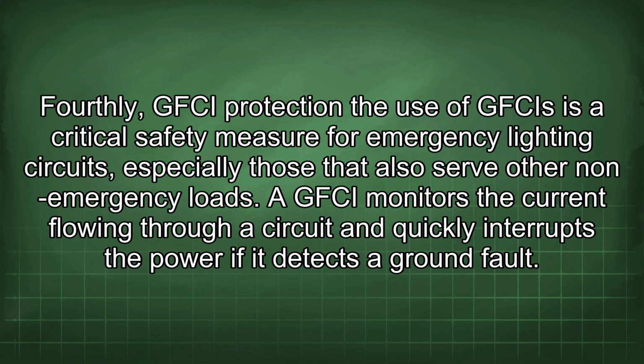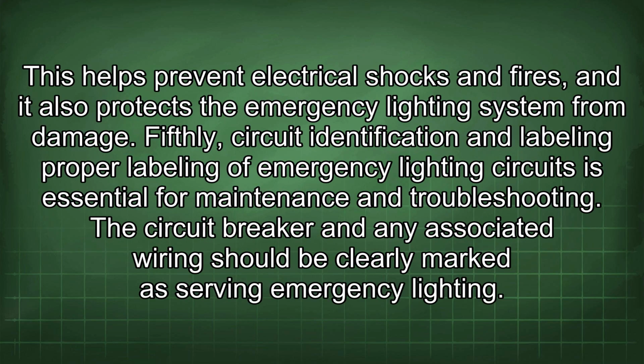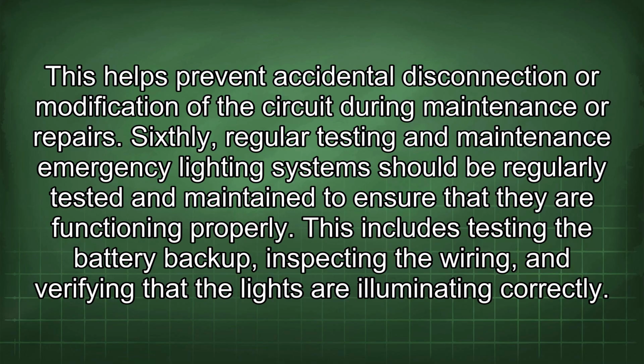Fourthly, GFCI protection. The use of GFCIs is a critical safety measure for emergency lighting circuits, especially those that also serve other non-emergency loads. A GFCI monitors the current flowing through a circuit and quickly interrupts the power if it detects a ground fault. This helps prevent electrical shocks and fires, and it also protects the emergency lighting system from damage. Fifthly, circuit identification and labeling. Proper labeling of emergency lighting circuits is essential for maintenance and troubleshooting. The circuit breaker and any associated wiring should be clearly marked as serving emergency lighting. This helps prevent accidental disconnection or modification of the circuit during maintenance or repairs.